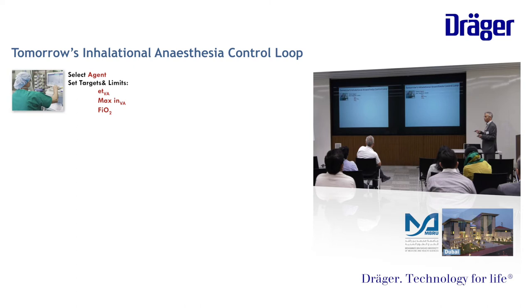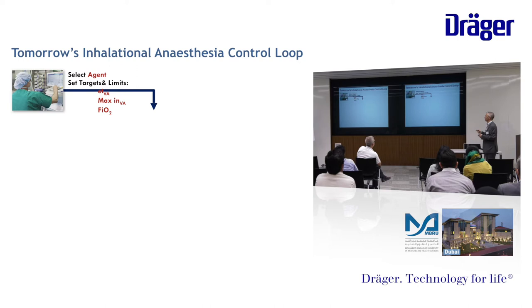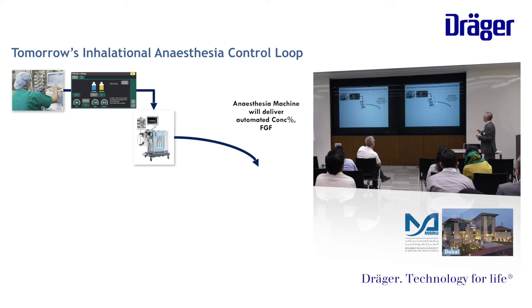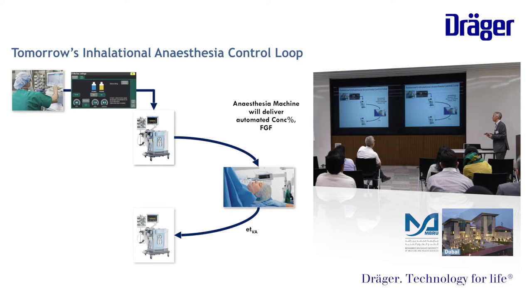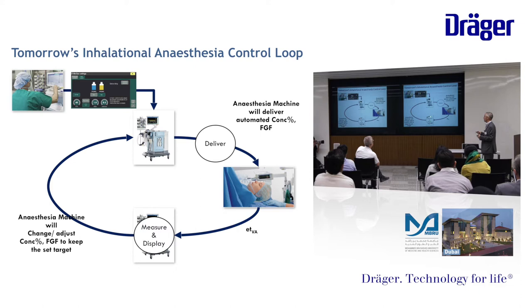Tomorrow's inhalational anesthesia that we are aiming to target: select the agent, select the end-tidal volatile anesthetic that you need, select the maximum inspiratory volatile anesthetic the machine can deliver — which is the maximum allowable — and select your FiO2. And the machine will do it. It will deliver to the patient, the patient will give us the output which is the end-tidal volatile anesthetic, and the machine will react and keep the cycle. So it is delivering, measuring, displaying and taking decisions, while the operator is just controlling and modifying the strategy. This is what is called closed loop control.